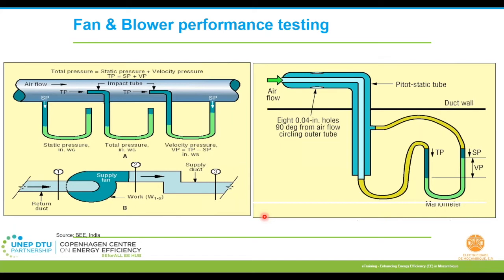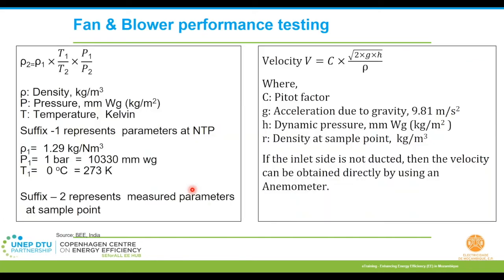Fans and blowers, this is slightly complex, but basically you'll be needing an instrument called a manometer. It can be either portable or already installed if you have a BMS system in place and you are capturing all these data. So basically you'll be measuring the pressure in the ducts, both on the return side and the supply side. And this is again for your later reference. I have given a step-by-step process for how to evaluate the efficiencies of the fans and blowers.